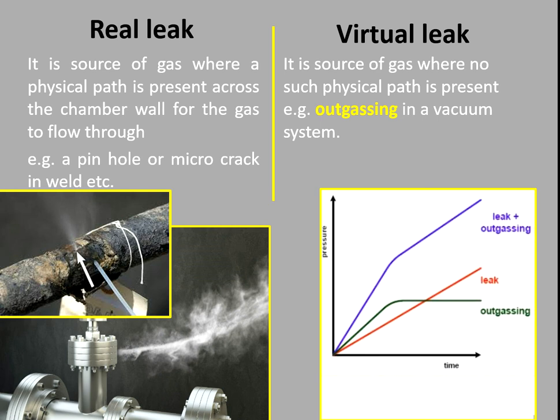A virtual leak is a source of gas where no physical path is present. An example is outgassing in a vacuum system. Outgassing means when a chamber is under vacuum, gases trapped in the metal during the manufacturing process get released. In the graph, the green curve shows pressure increasing from zero up to a certain limit and then becoming constant, as there is no more gas trapped inside the material.